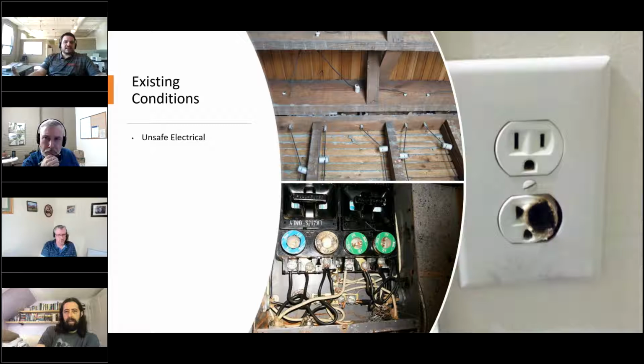Well, I had a sign off by an inspector. Well, about half the time they find a strand that's still live somewhere in the home. It's shocking how much live knob and tube there's still left in homes. And inherently by itself, it's not necessarily unsafe, but if you want insulation in those cavities, yeah, you need to have it removed. And of course, exposed panels, ungrounded outlets, all major hazards.